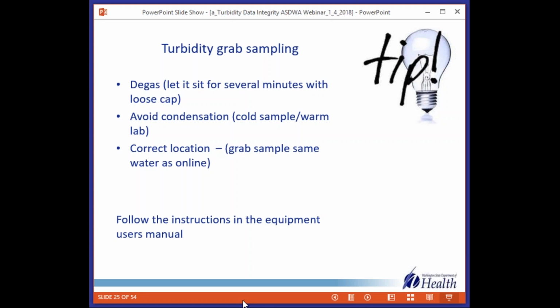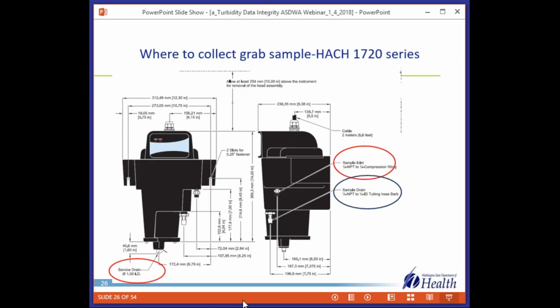And then correct location. And in this case, correct location is we want the exact, or as close as we can, same water that the online instrument is measuring. This is a different issue from, are we sampling in the correct location for determining turbidity through a filter? When we're looking at verification, we want the same water as the online instrument. So let's take a little closer look at that, where that right spot is.